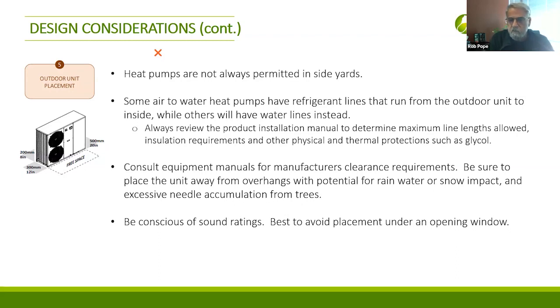And it really boils down to one thing generally, and that's the sound levels. In many jurisdictions, not all of them, there's a requirement that at the point of reception, which is typically the property line, your neighbor's fence, for example, the noise of the heat pump cannot exceed 45 decibels, right? And that's what they're worried about. There's ways around that. We have successfully dealt with authorities with jurisdiction to convince them to let us put that heat pump there, because we've measured this decibel level from the manufacturer's data, and we can see that at 3 feet or 1 meter or 2 meters from the unit, our decibel level will be at an acceptable level, but we have to prove that.